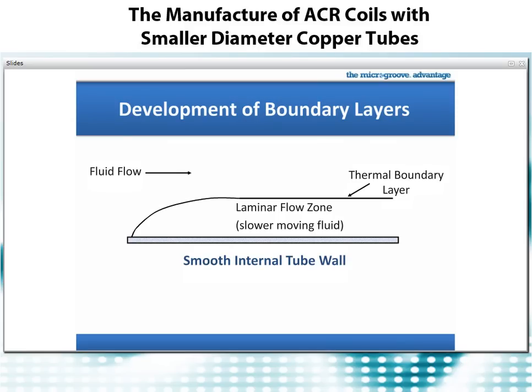Whenever fluid moves through a tube, the fluid closest to the tube wall behaves differently than the fluid in the center. The fluid next to the tube wall sets up a boundary layer, in which heat transfer becomes more difficult. This applies to the hydraulic motion of fluid as well as the way heat moves from the center of the tube to the tube wall. Fluid closest to the tube wall tends to move slower, and even in turbulent flow, a laminar sub-layer forms. Heat moves slower through these boundary layers, which act as an insulator interfering with the heat transfer we want. In a smooth tube, the boundary layer develops and does not dissipate or go away.